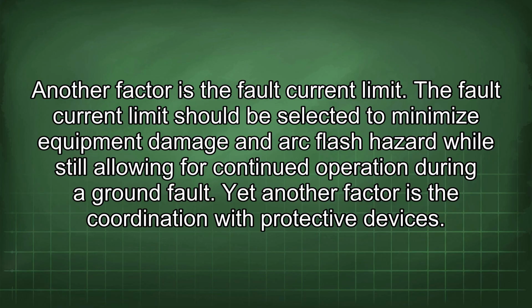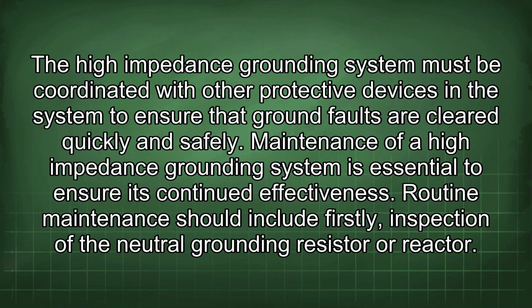Yet another factor is the coordination with protective devices. The high-impedance grounding system must be coordinated with other protective devices in the system to ensure the ground faults are cleared quickly and safely. Maintenance of a high-impedance grounding system is essential to ensure its continued effectiveness.